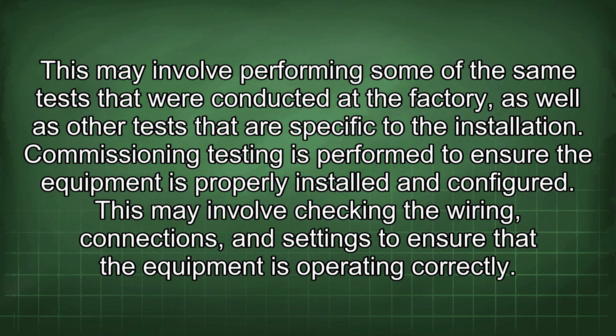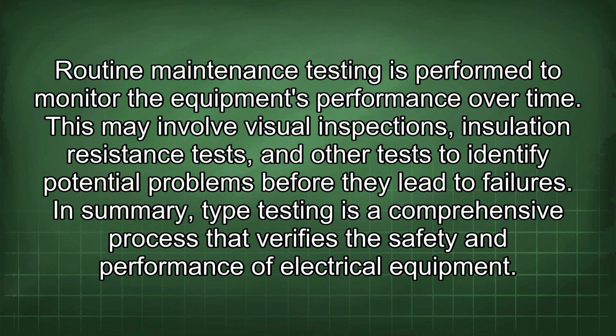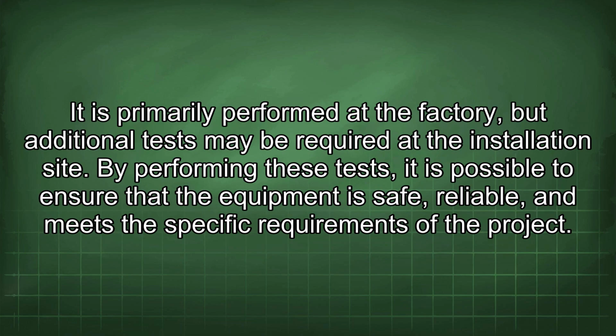This may involve checking the wiring, connections, and settings to ensure that the equipment is operating correctly. Routine maintenance testing is performed to monitor the equipment's performance over time. This may involve visual inspections, insulation resistance tests, and other tests to identify potential problems before they lead to failures. In summary, type testing is a comprehensive process that verifies the safety and performance of electrical equipment. It is primarily performed at the factory, but additional tests may be required at the installation site.